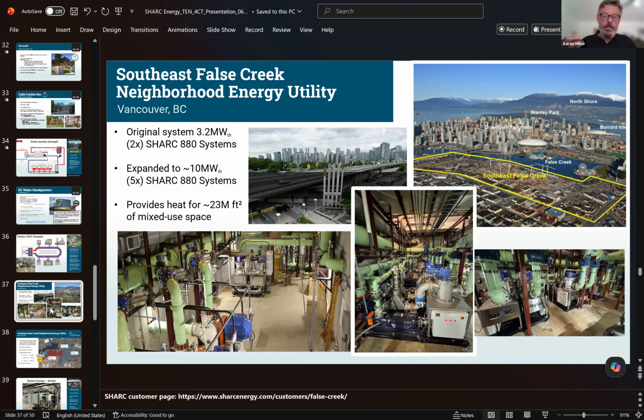But to answer your question, the easy winners are when you can get that natural collection spot: lift station, pump house, wastewater treatment plant, and then ideally one of those assets is nearby an off-taker. Because as I mentioned before, in an ideal world, your wastewater source, your tank, and your SHARC plant are really close to each other, because we're trying to move the wastewater around as little as possible. In an ideal world, your apartment complex or your hospital or your prison, whatever it is, is right nearby. So all we have to do is essentially horizontally bore over to connect that building and send that condenser water into the building. That's really what you're looking for.